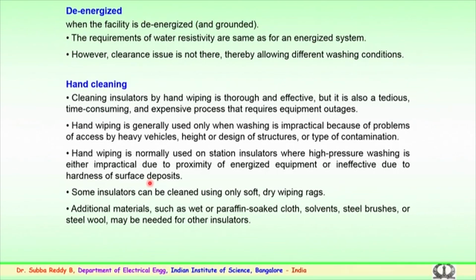So, here again various methods are adopted for the cleaning. We will discuss some of the methods and techniques which are used for the de-energized situations. One is hand cleaning. It is basically the cleaning of insulators by hand, wiping thoroughly and effectively on the insulator surfaces, removing the dirt and pollutants which are spread on the surface. But it is a tedious, time consuming and also expensive process which requires a lot of equipment outages. So, the outages for the maintenance, the time taken with the equipment de-energized, require a long process and also a tedious job.